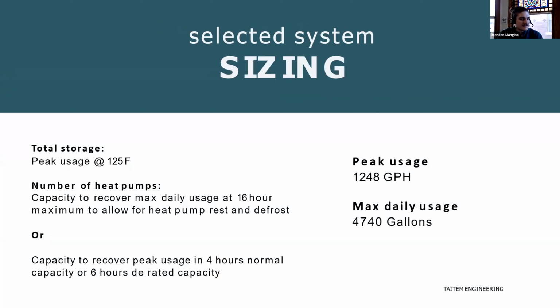So when sizing these systems, working with Sanco, I like to size the peak storage, or the total storage, to deal with the peak usage. And that's an hourly usage of 1 to 3 hours, typically in the morning. So we needed a total storage of 1,248 gallons roughly. And then sizing the number of heat pumps, or the generation, we choose whichever of these quantities is the largest. The first one is the capacity to recover the max daily usage in a 16-hour period. This allows for the heat pumps to rest and defrost, and makes it so we're not pushing them to the max 24/7.